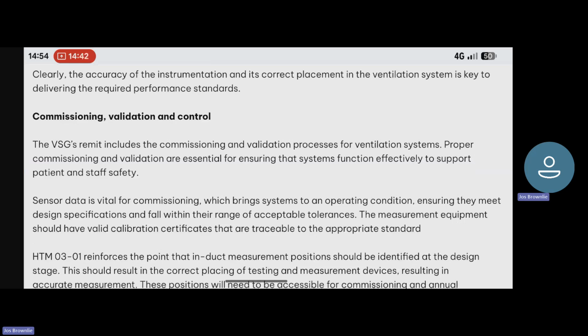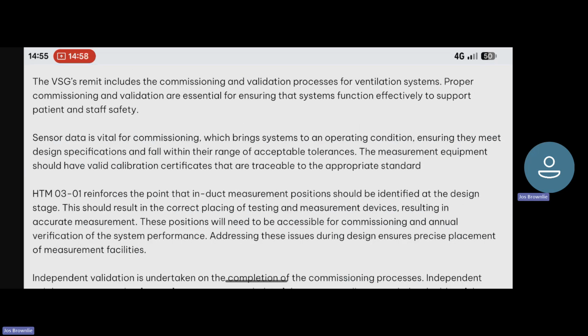The VSG's remit includes the commissioning and validation processes for ventilation systems. Proper commissioning and validation are essential for ensuring that systems function effectively to support patient and staff safety. Sensor data is vital for commissioning, which brings systems to an operating condition, ensuring they meet design specifications and fall within their range of acceptable tolerances. The measurement equipment should have valid calibration certificates that are traceable to the appropriate standard.